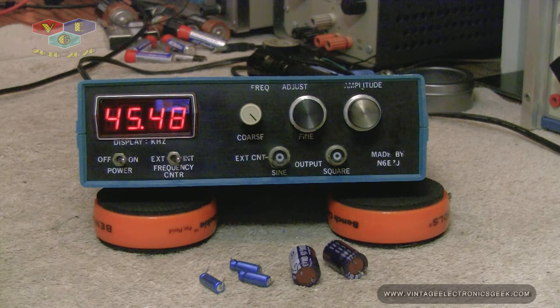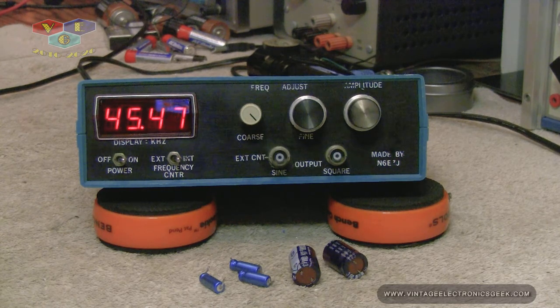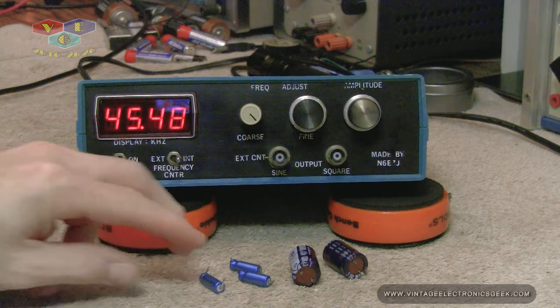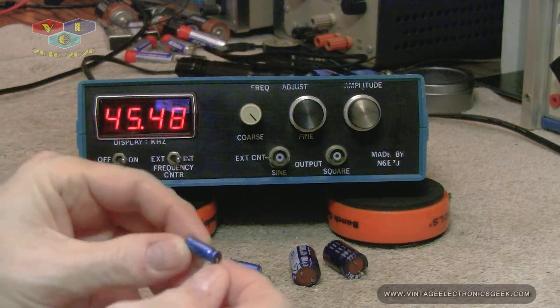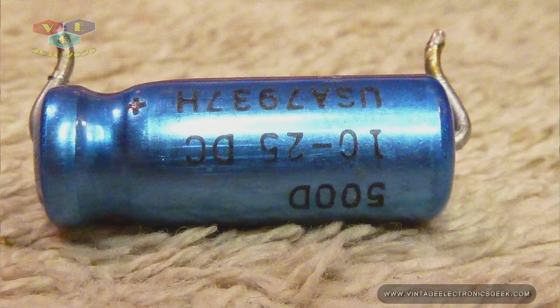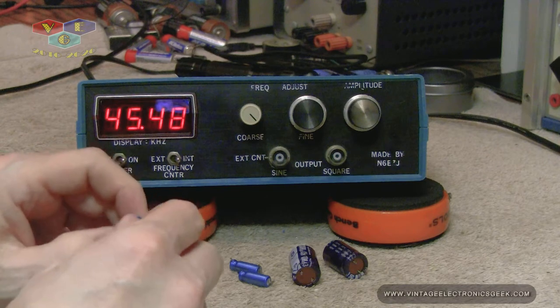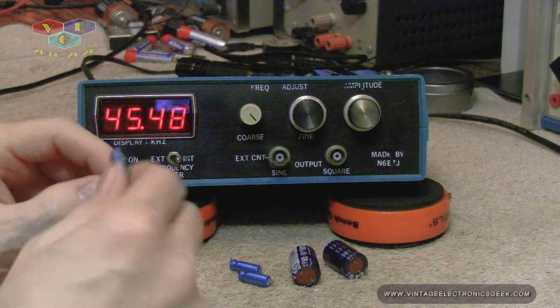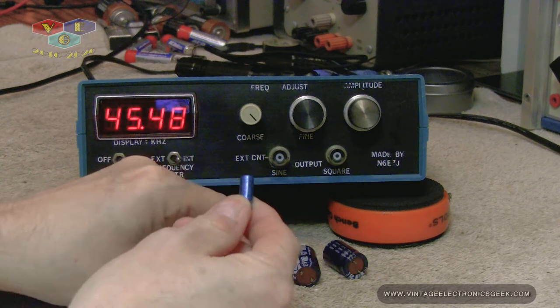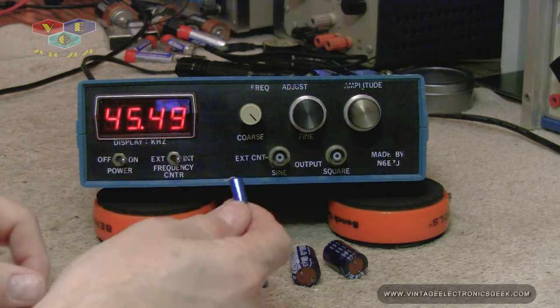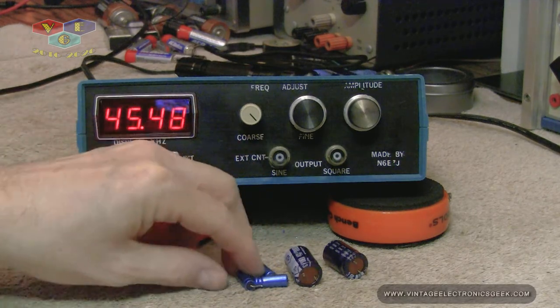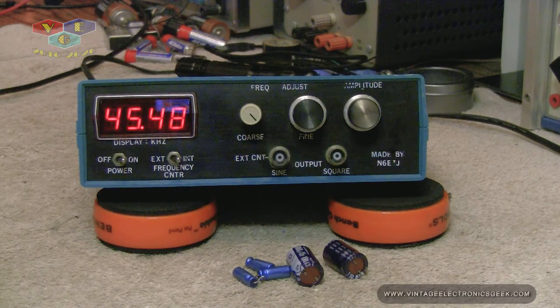And those ones actually tested good. I pulled them out of the board, tested them. I figured, well, I've got them out, I'm just going to go ahead and replace them with new ones. These little blue ones are Spragues, and they're 10 microfarads at 25 volts. These ones, all three of these did check high ESRs, so I went ahead and replaced them with modern day. And everything is fat and happy.